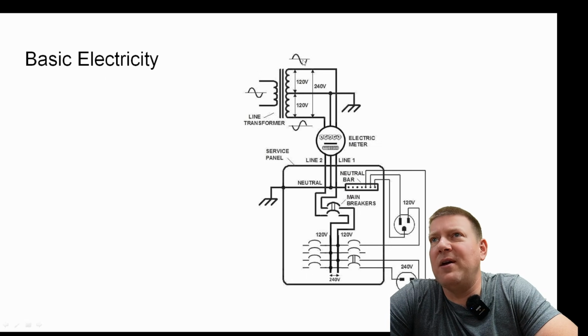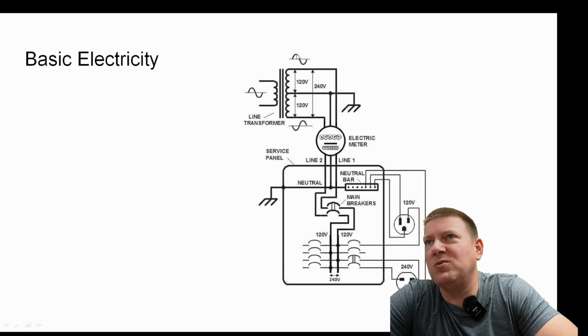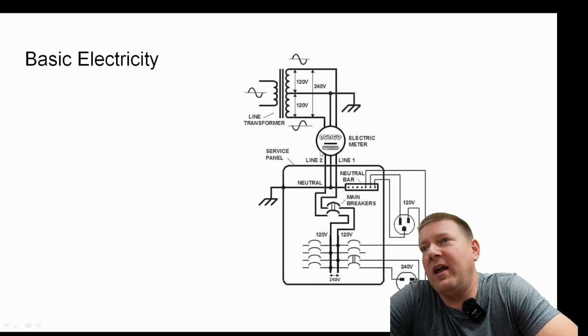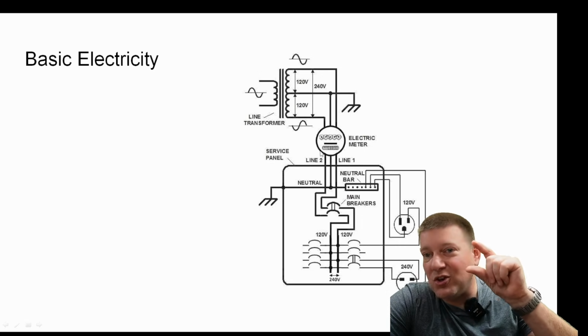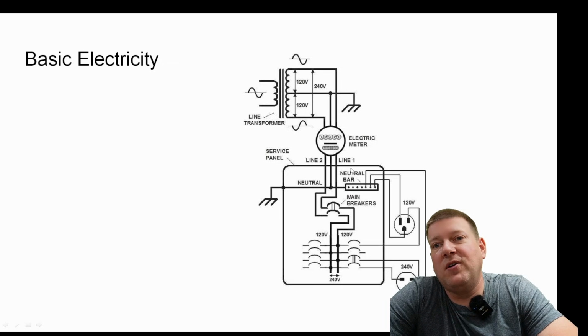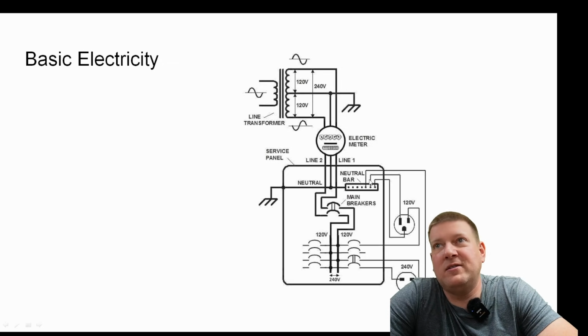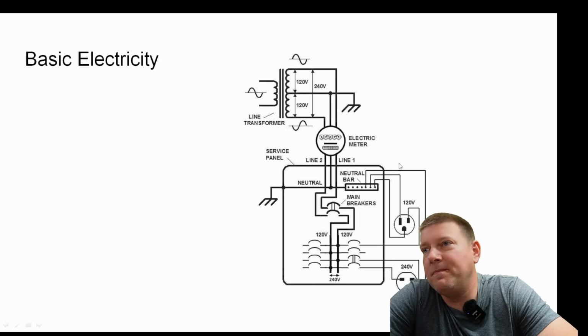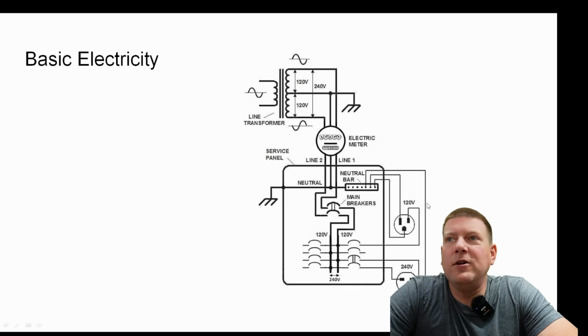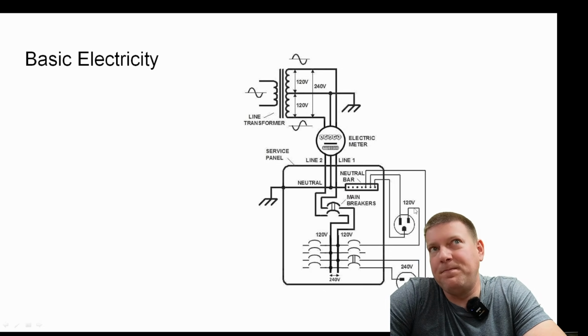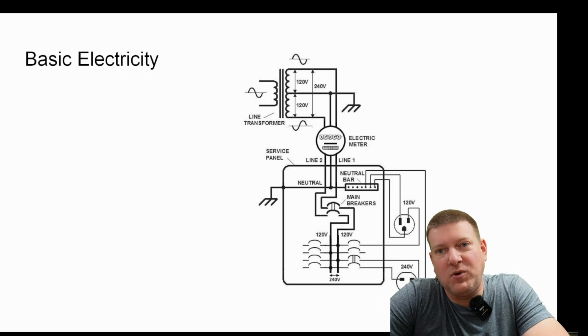And you can actually see that right here in the pictogram. You can see this one here is 180 degrees out of phase with this one, and the difference of potential. So you got two waves that are doing this. The difference of potential is going to be RMS 240 volts, okay? So you have to understand that it's based off of ground, right?